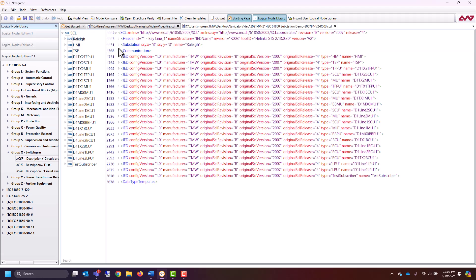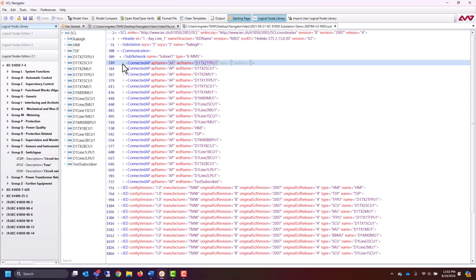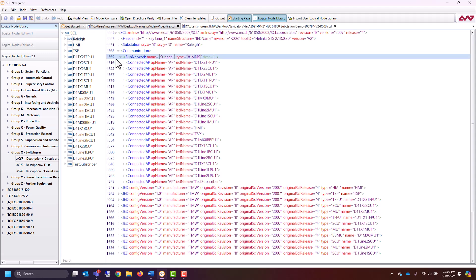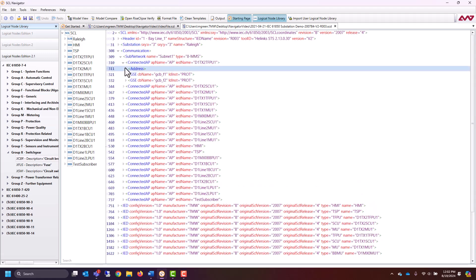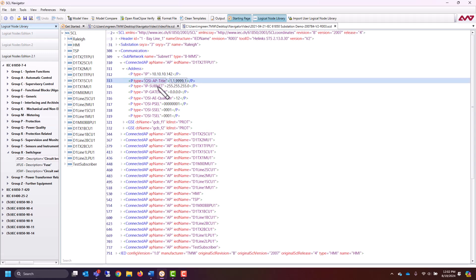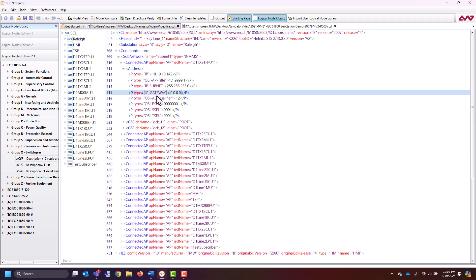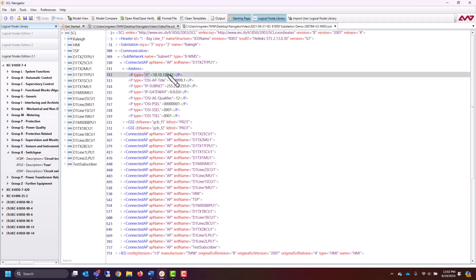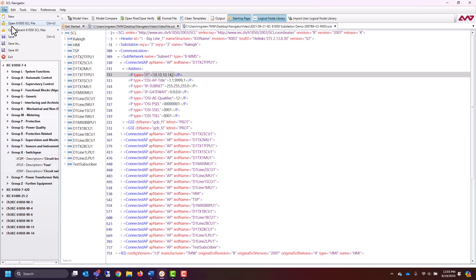You can also take a look at the communication section and see all of the different access points. You can open them up individually and see their IP addresses, their gateways, any of the qualifiers, and any information like that. And of course, if the device sent to you is not properly configured, you can come in here and make changes just like always. After you make any changes, you can go to File, Save As to export your file and be ready to import it into your individual IEDs.